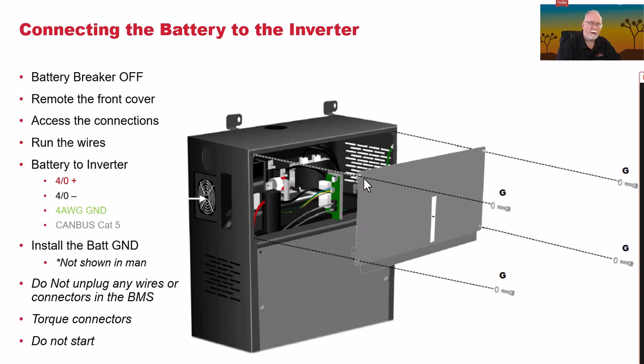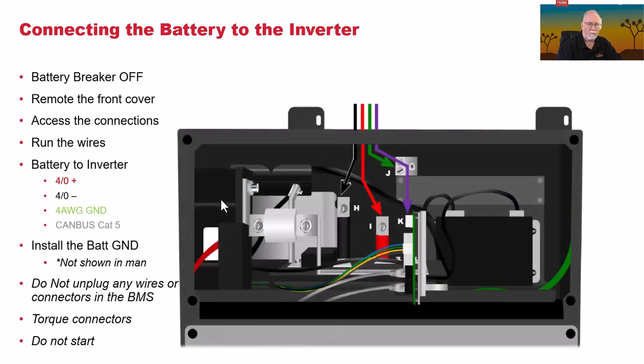So the top panel of the battery is where all the connections are made. So remove this front cover by removing the 5mm hex heads that are inside of it, the 4 Allen heads. Then access the connection. You're going to run your wires as needed between the inverter and the battery. You're going to have a 4-aught plus, a 4-aught minus, a 4-gauge ground cable, and a CAN bus, which will be a Cat5. There is an installation of an additional cable for the battery ground.